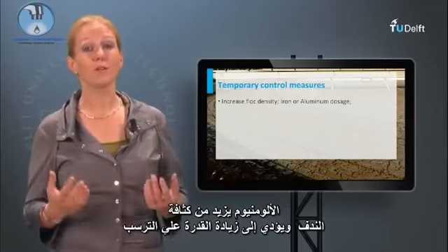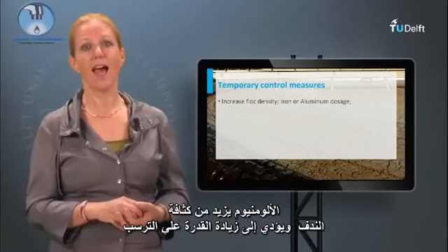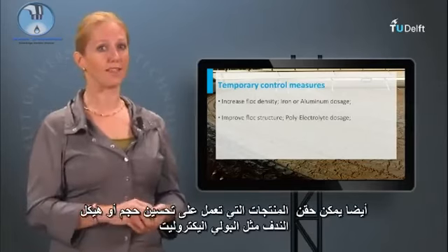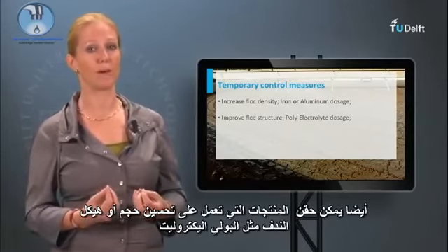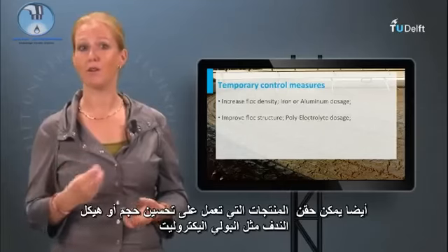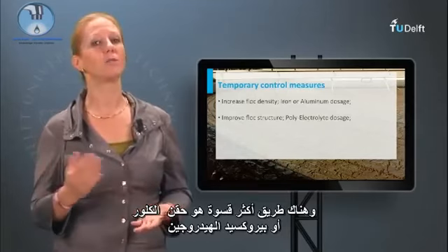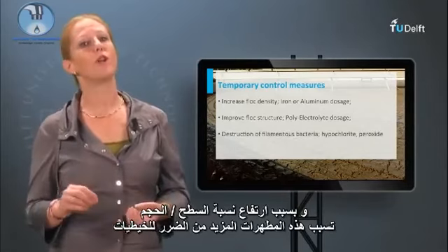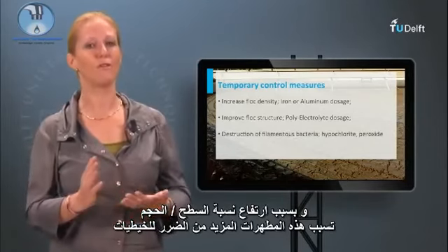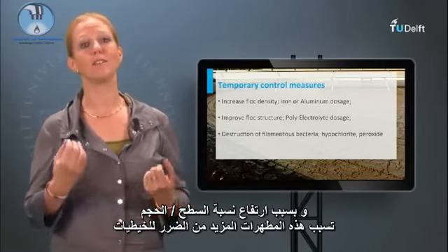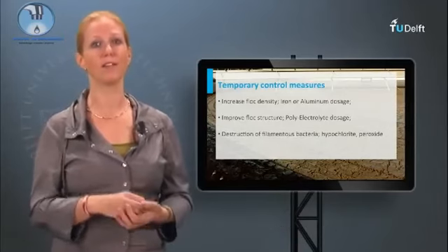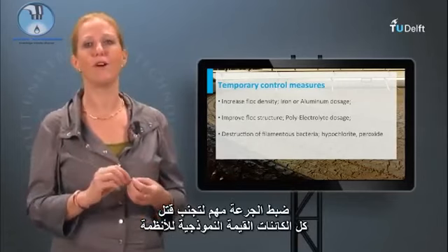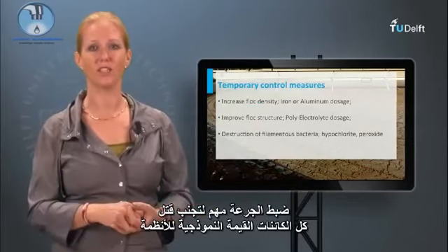The aluminium increases the density of the floc and leads to increased settleability. Also, products that improve size or structure of the floc can be dosed, like polyelectrolytes. A more harsh method is chlorine or hydrogen peroxide dosing. Due to the high surface volume ratio of filaments, these disinfectants will bring more harm to the filaments than to the floc formers. The dosage is important to avoid killing the entire population.